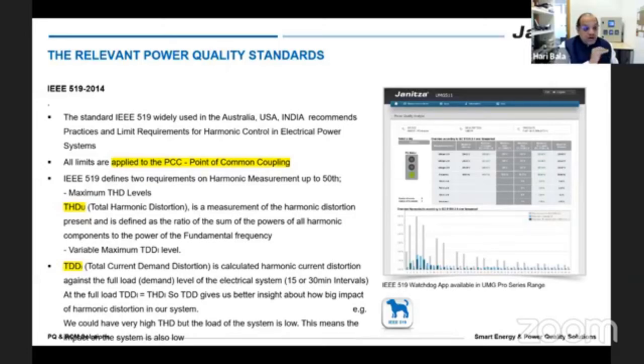Right now, TDD is a parameter which is introduced in IEEE 519. What is TDD? TDD is basically the total demand distortion. Generally, THD is calculated with respect to the fundamental frequency, whereas TDD is calculated with respect to the load taken by the consumers over a period of time. So the reference for harmonic measurement is made easier by IEEE 519 by measuring TDD for the consumers. That's a very valid point.